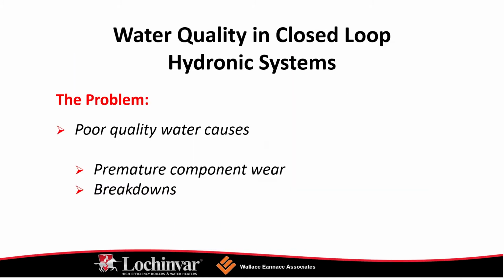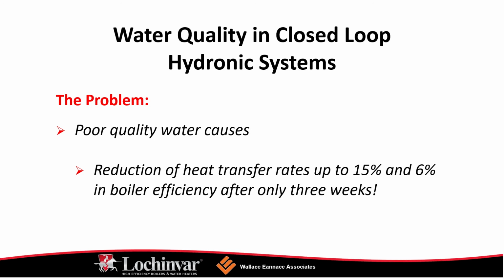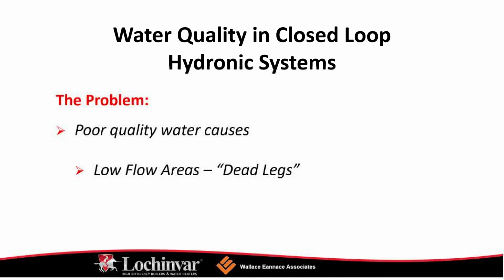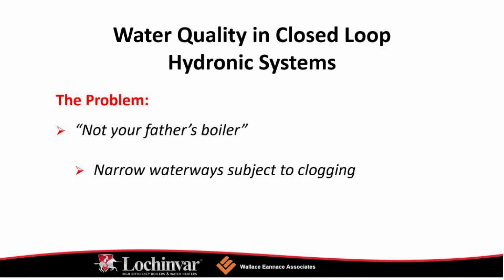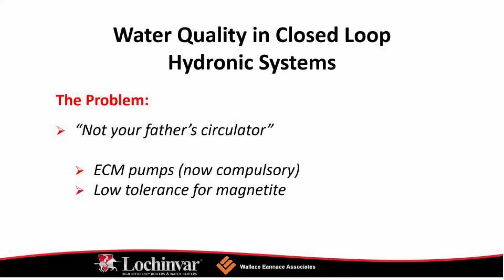So water quality is always an issue, certainly in closed loop hydronic systems. Leads to failures, general corrosion, basically loss of efficiency and failures, in a nutshell, is what poor water quality conditions result in. We're going to use up more fuel when competing against this type of condition. We're going to have more units down, and we're going to see an increase in callbacks.